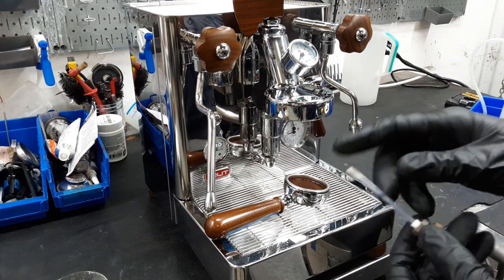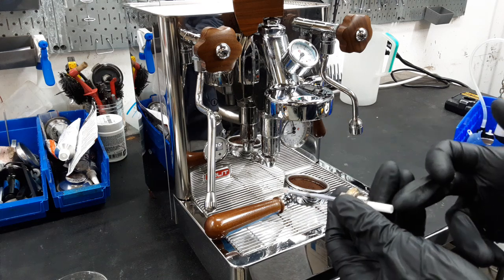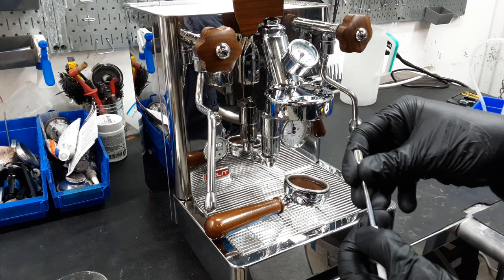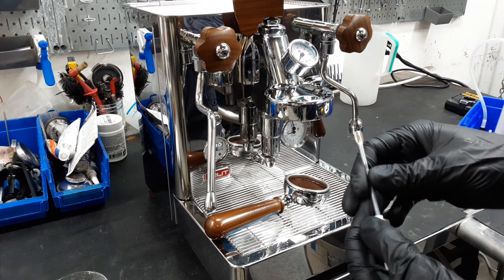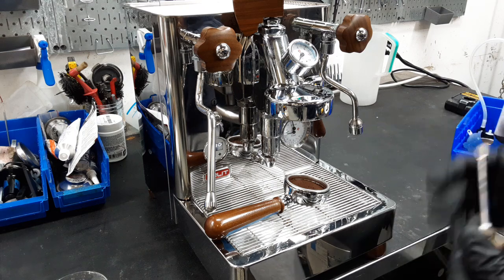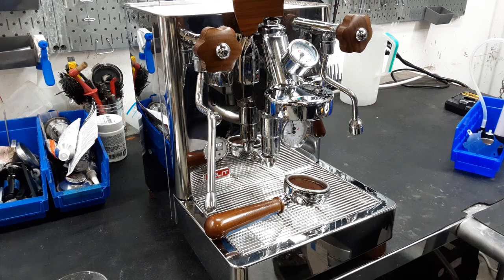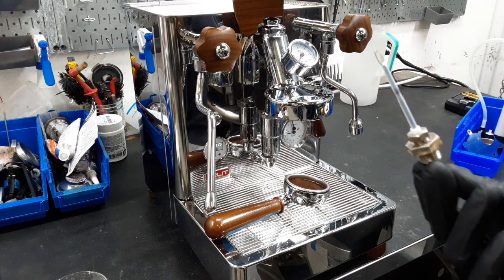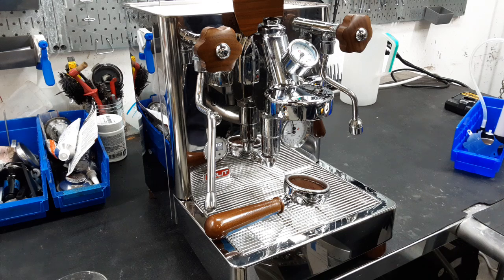The reason you don't want that to go up and down is because if you pressurize your boiler, this will slowly go up and then add more water, go up, add more water, till you're overflowing. And so what we did is we had to open the boiler from the bottom through the heating element. We had to go in there and take it out by hand and then reseal the boiler, and then we put a brand new water level probe inside of your boiler.